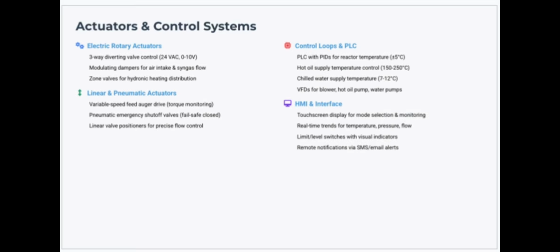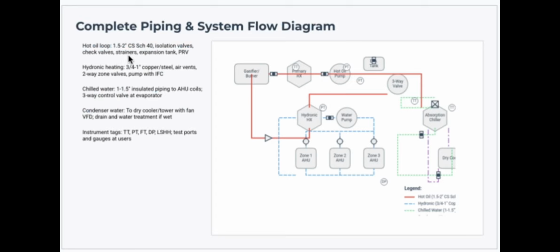Control loops and PLC with PIDs for reactor temperature, hot oil supply temperature control, chilled water supply temperature, and VFDs for blower, hot oil, and water pumps. HMI interface, touchscreen display for mode selection and monitoring, which shows real time trends for temperature, pressure, and flow, limit/level switches with visual indicators, and you can receive notifications of the system through text messages and emails.